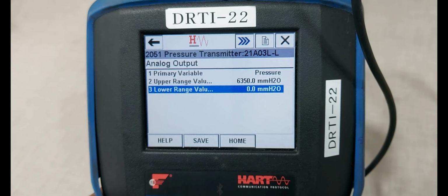Okay, remove the pressure from the unit. Now output is showing 3.999 and 4 milliamps. Display is showing 0 mmH2O and 0%. We have already applied the static pressure to both sensors. Now we are applying equal pressure.